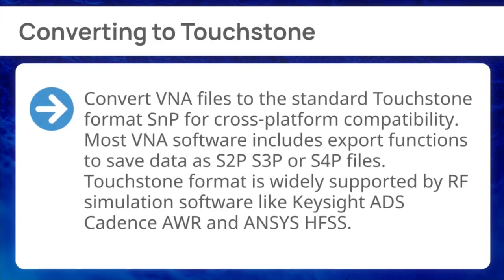Convert VNA files to the standard Touchstone format, SnP, for cross-platform compatibility. Most VNA software includes export functions to save data as S2P, S3P, or S4P files. Touchstone format is widely supported by RF simulation software, like Keysight ADS, Cadence AWR, and ANSYS HFSS.